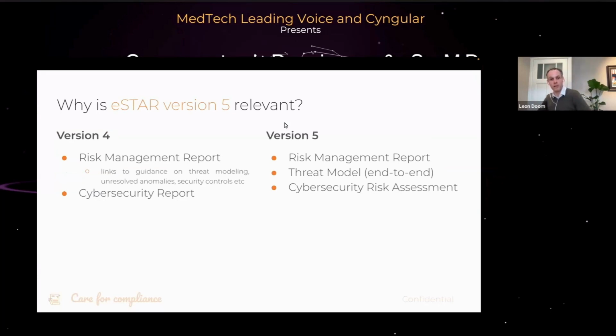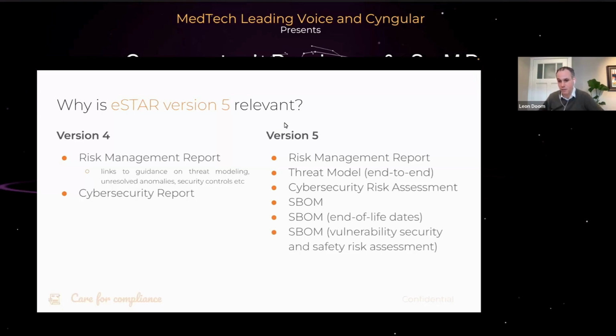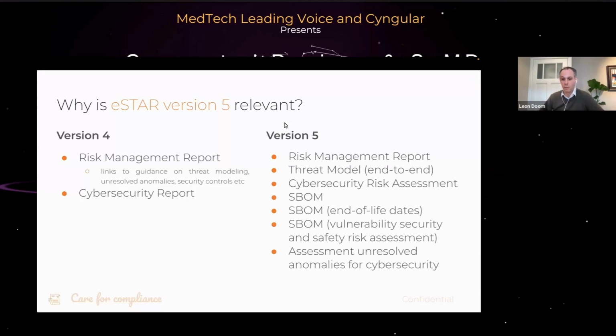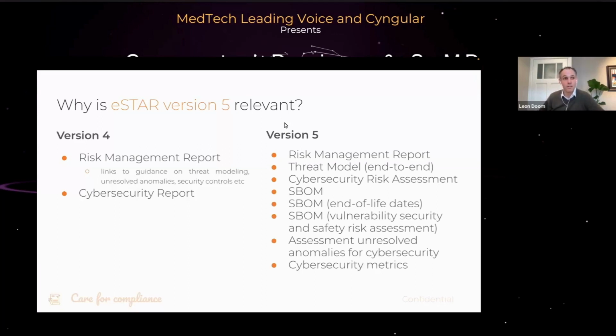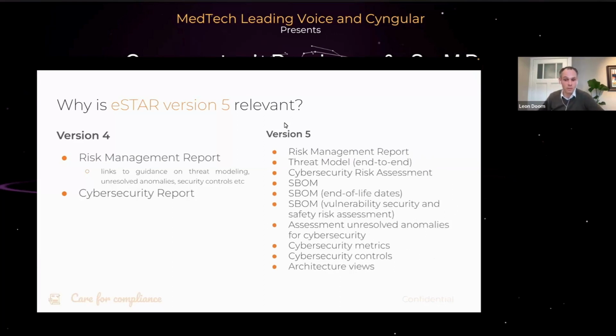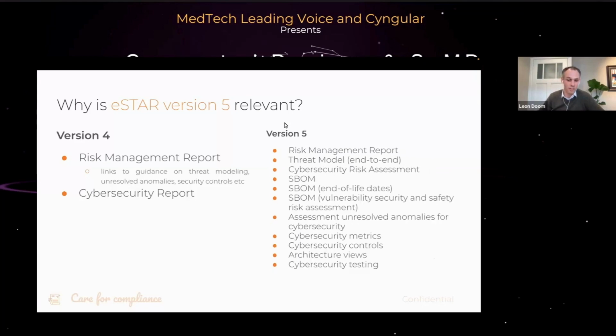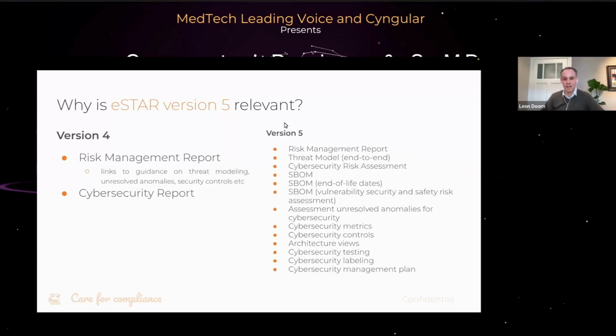So if you look at the differences between version 4 and version 5 of the eSTAR, clearly version 4 already required a risk management report with a clear cybersecurity assessment to be delivered as part of the 510K and a cybersecurity report. Then if you look at version 5, again, also the risk management report, the threat modeling, end-to-end cybersecurity risk assessment, SBOM, for those who are unaware of what that means, it's the software bill of materials. Also one with all the end-of-life dates, then one with the vulnerability, security, and safety risk assessment. Then also an assessment of the unresolved anomalies for cybersecurity. The cybersecurity metrics, what that means, we'll touch on it further on. Cybersecurity controls, the architecture views, the cybersecurity testing, the cybersecurity labeling, and the cybersecurity management plan.